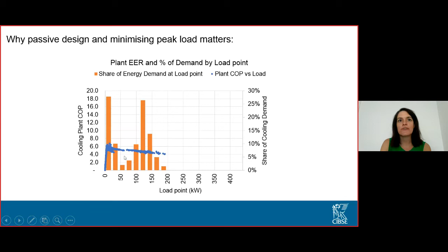And then moving on to rethinking the mechanical systems that we put into offices. How are we air conditioning offices? Within the modelling and simulation, we looked at two different system alternatives: a variable air volume system on the left and a fan coil unit system on the right. Obviously, the variable air volume delivers a lower energy intensity, given its free cooling potential and low pumping energy, primary only, not secondary. It's an easy to control system as well. However, to get an SFP of 1.2 watts per litre per second, that's going to require larger ducts or rethinking how that system delivers air.